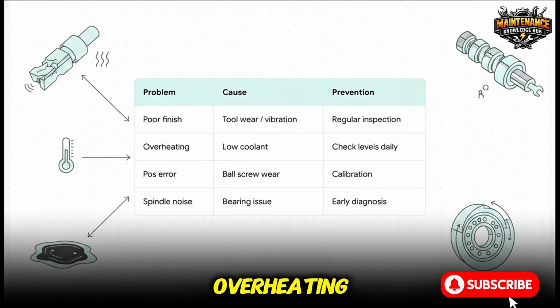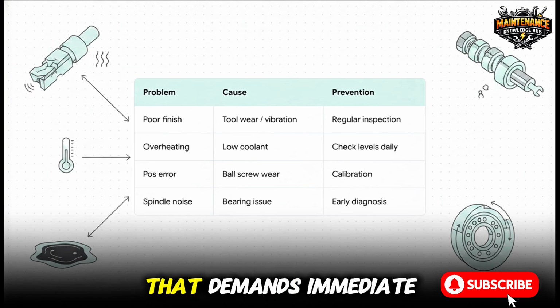If the machine is overheating, you probably have low coolant or lubrication, which is exactly why we do daily level checks. Getting positioning errors where the machine cuts in the wrong spot? That's likely wear and tear on those highly precise ball screws, meaning it's time for calibration. And if you hear a grinding noise in the spindle, that is almost certainly a bearing issue that demands immediate, early diagnosis.